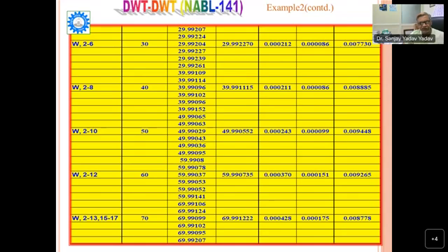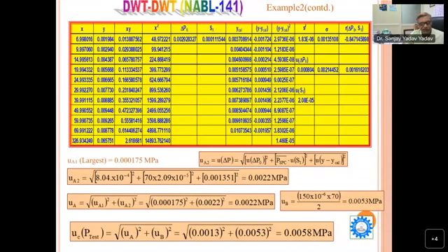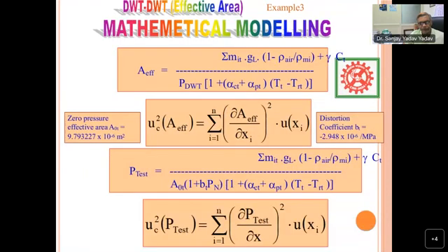At the different pressure points, it is repeated, and after this you have to make a least squares fitting. This Excel sheet is prepared for you people only. Here is the x value, here is the correction value. You can make xy, you can make x square, and then using those equations you can determine delta P0 S and the correction value. And after all this you can determine the uncertainty of the slope and intercept, and then determine the exact uncertainty value. And this mathematical modeling is for effective area.